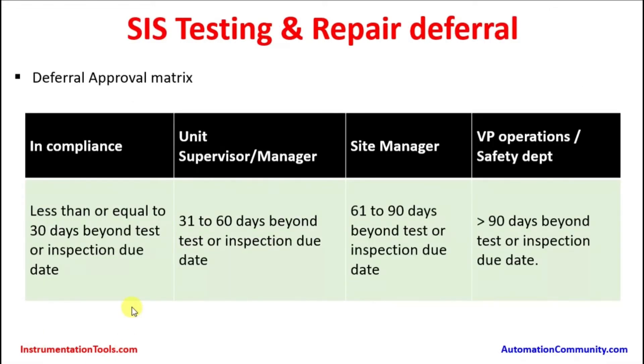Deferral approval matrix: a deferral of 30 days or less beyond the inspection due date is considered in compliance. When the deferral goes between 31 to 60 days beyond the inspection due date, it requires unit supervisor and manager approval. From 61 to 90 days beyond the scheduled interval, site manager approval is required. When the deferral goes beyond 90 days of the test due date, it requires approval from the vice president of operations and the safety department in charge.